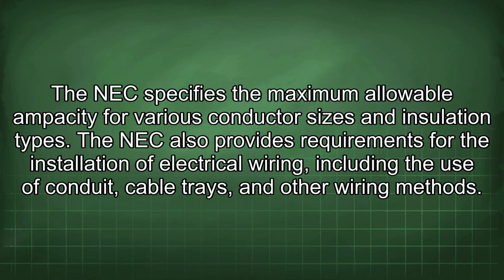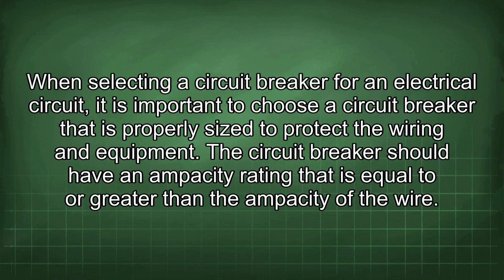The NEC specifies the maximum allowable ampacity for various conductor sizes and insulation types. The NEC also provides requirements for the installation of electrical wiring, including the use of conduit, cable trays, and other wiring methods. When selecting a circuit breaker for an electrical circuit, it is important to choose a circuit breaker that is properly sized to protect the wiring and equipment.